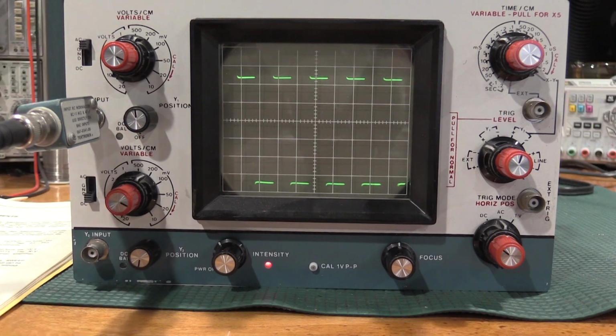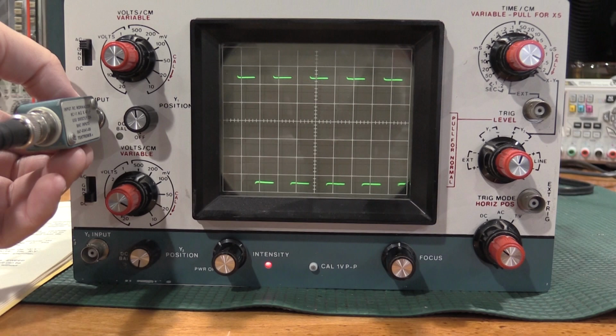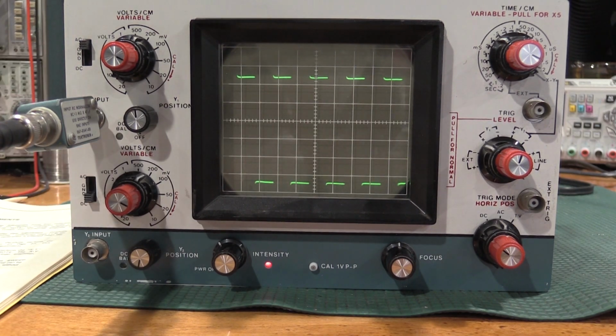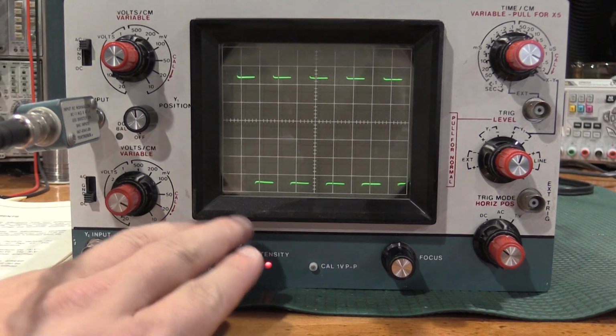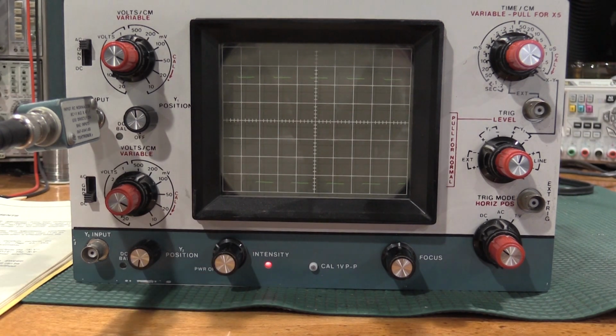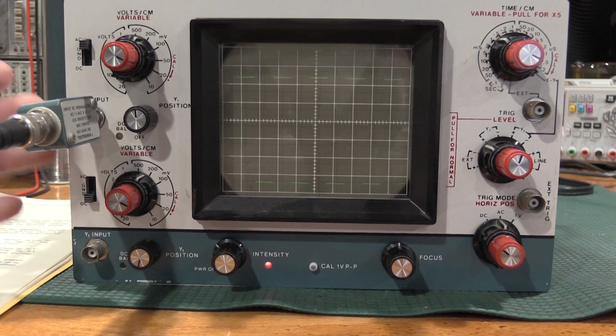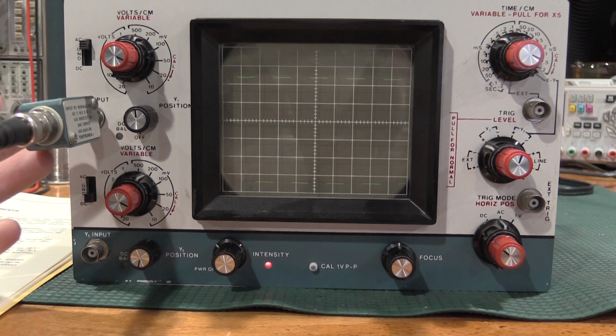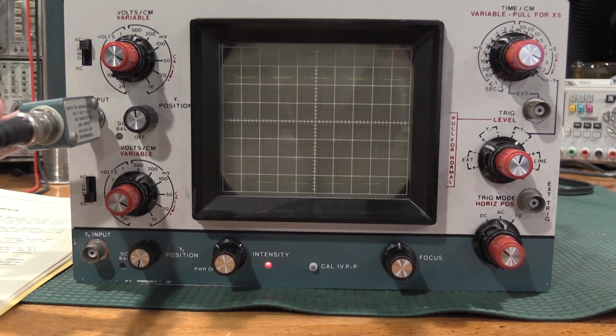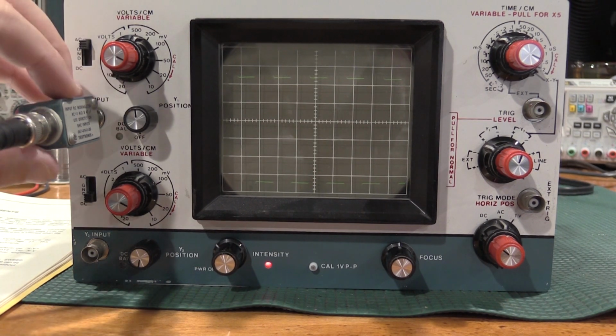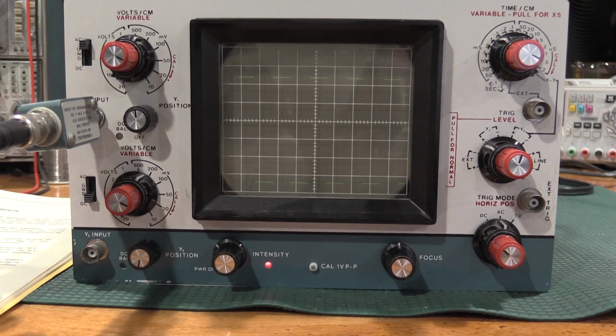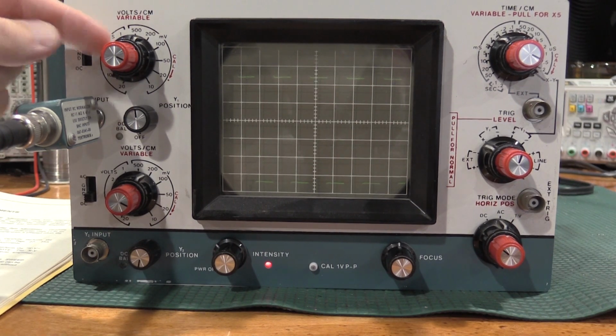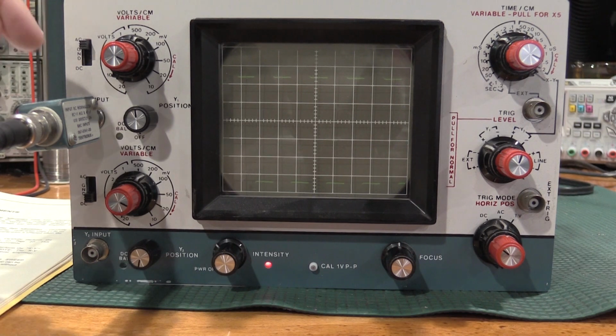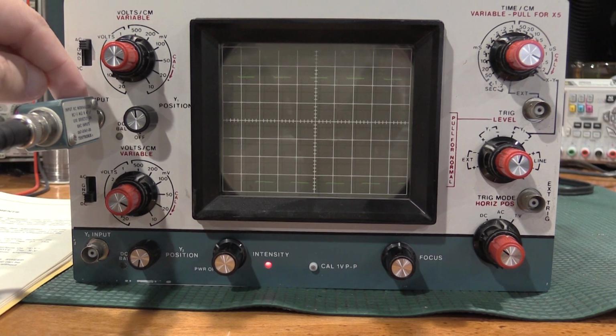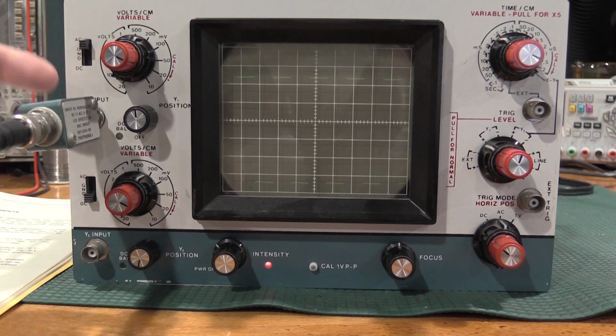So when you're doing a scope adjustment, one of the things to be cautious of is you don't want to normalize to the exact input of the scope. If you're doing measurements where the coupling of the input of the scope is of primary concern, this isn't the scope that you're going to be using. You're going to be using something much more modern, much newer. What's going on here is by adjusting this and setting it once and then not touching it throughout the calibration process, you're adjusting all the attenuators to match each other. That's the important part, is they match each other. Less so have an exact input impedance here, just that you don't have to readjust the probe every time you change the attenuation.